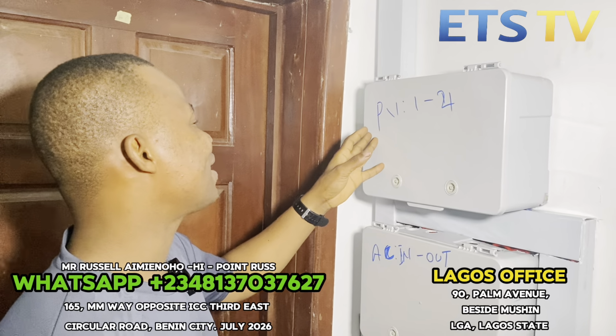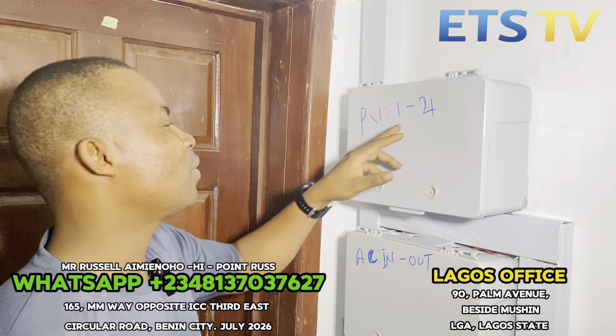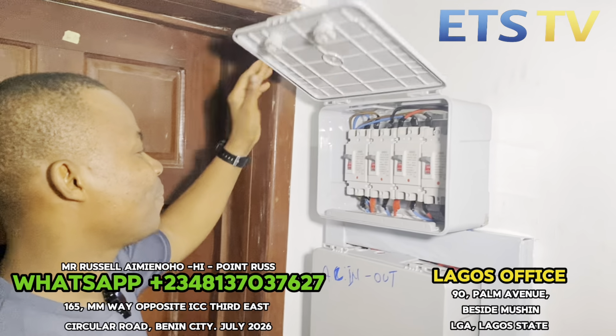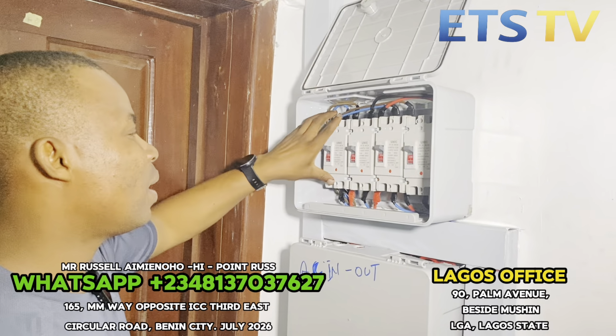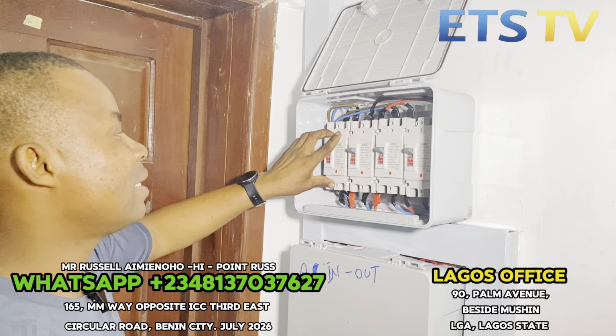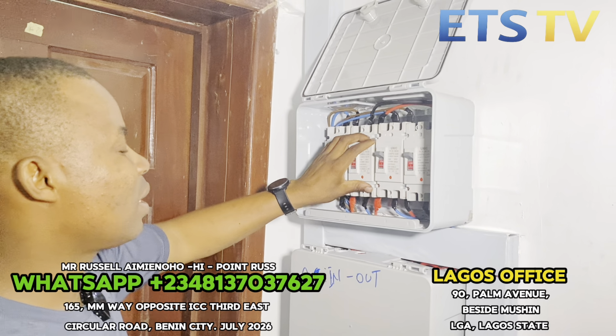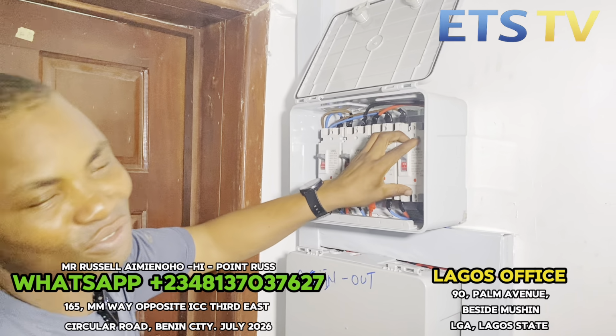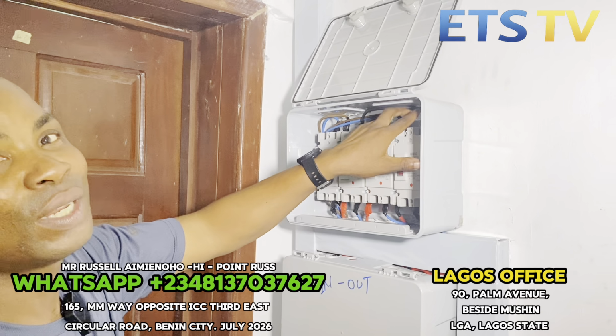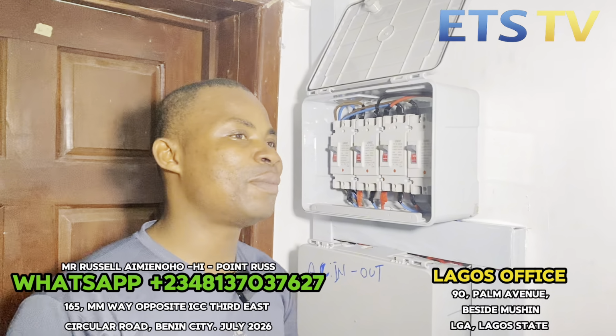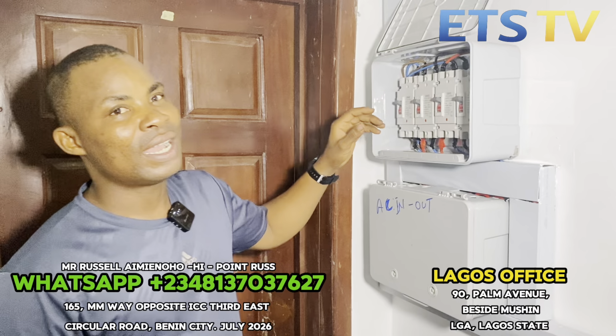Here is the PV side, we have breakers 1 to 4, that's 4 breakers. On breaker 1, we expect 15 solar panels, breaker 2 has 15 solar panels, breaker 3 has 15. The fourth has no solar yet, that's why nothing is connected to it. When Oga plans to add the remaining 15 to make 60, we'll add on that joiner.